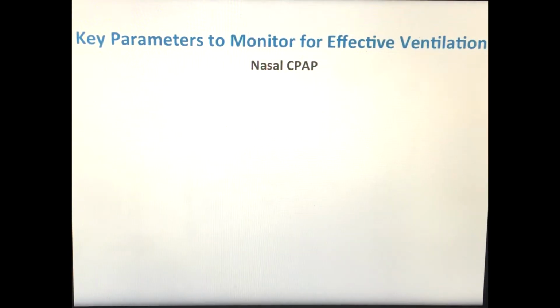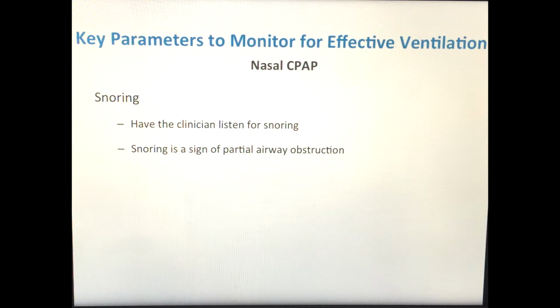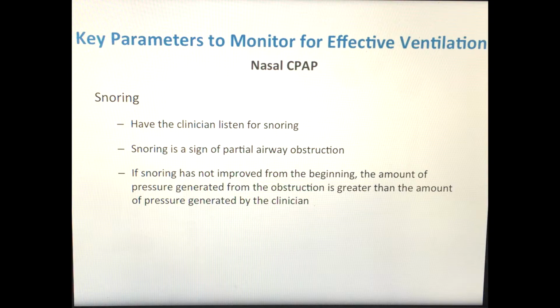The final key parameter you want to have the anesthesiologist measure and monitor is snoring. You want to have the clinician listen for snoring just as the patient starts to fall asleep. This is a sign that the airway is partially obstructed. Next, once the pop-off valve is between 10 and 20 centimeters of water pressure and nasal CPAP is being applied, the snoring should get softer. What this implies is that the airway is opening up, becoming more patent, and allowing for more flow.